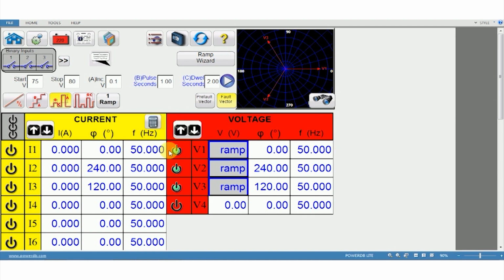Now finally, the pulse binary ramp. Now here the difference is really in the way it's tested. It's going to inject at 75 and directly go and inject at 80 volts just to ensure that it's going to operate within this limit. So if it's not operating at 80 volts, there is no point in continuing the test. It's like a shortcut to identify whether your values are right.